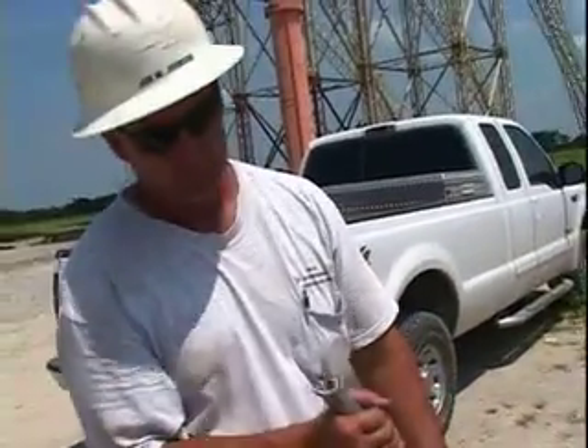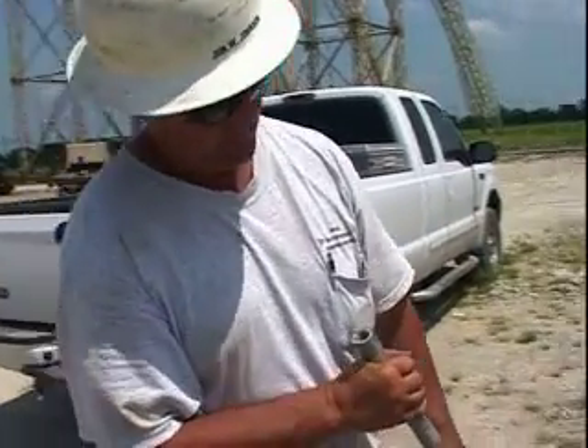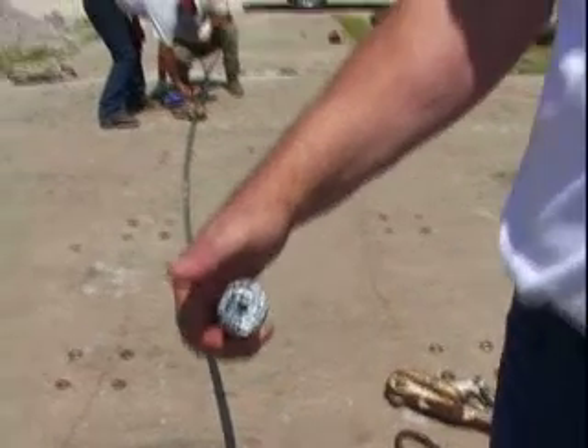The core hasn't moved hardly any. No it hasn't. Looks good — that's an A number one plus bonus there. Now we've got the sock ready for pulling the wire in through the running blocks, and the single groove strain clamp or sliding grips will hold the tension for us to do the sagging in the conductor for tensioning it, so we're ready.